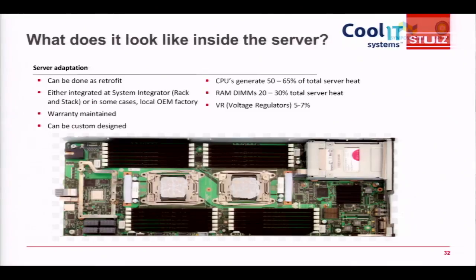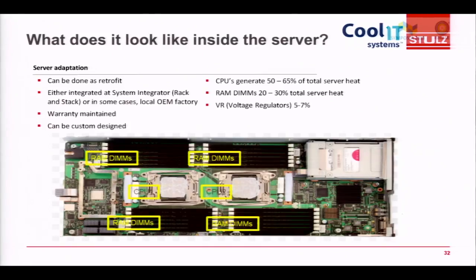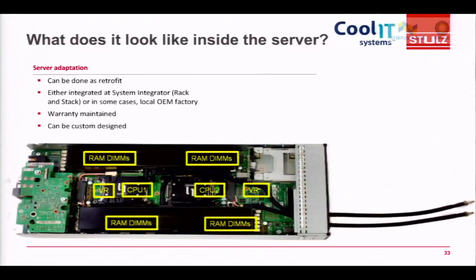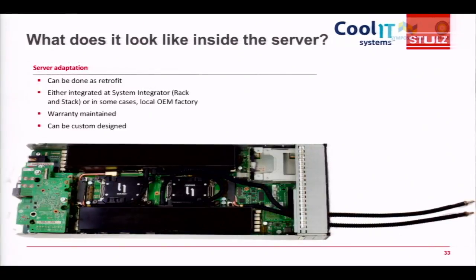How does it look? Typically, inside a server, you would have CPUs or GPUs, which are taking the majority of the power and generating maximum heat. You have voltage regulators, you have the RAM. All of these are what a server internally looks like, and generating the heat from here. This is where it is. And then, when you're able to have an engineering solution, and if you're able to connect via liquid cooling solutions and take away this heat directly at the source of generation, then you're bringing in a lot of efficiency, you're saving a lot of space. This is how it looks with the liquid cooling solution on board.